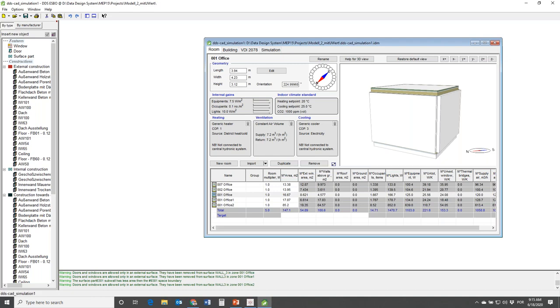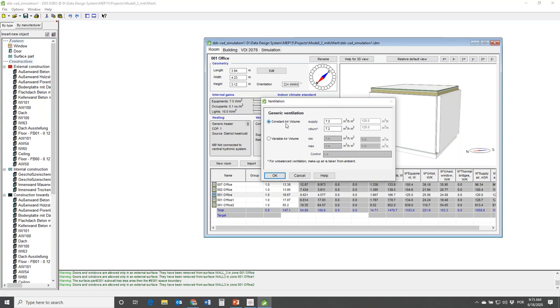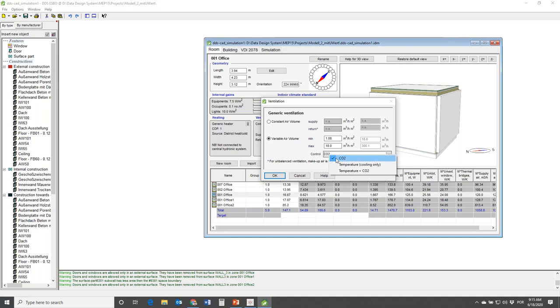Going down to Ventilation, you have the possibility to specify Constant Air Volume, but you can also have a Variable Air Volume system. With VAV, you can have it either temperature-controlled for cooling purposes, CO2-controlled, or a combination of both. This is a very neat function because during the cooling load calculation you can already specify characteristics of the air handling unit system, allowing a combined study of the room and the systems - already developing ventilation solutions as part of the cooling load calculation.